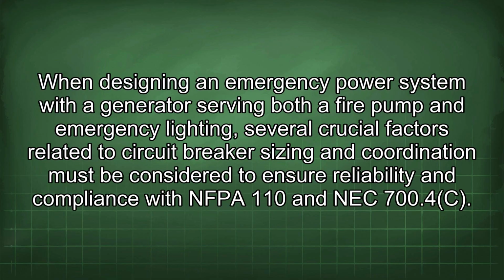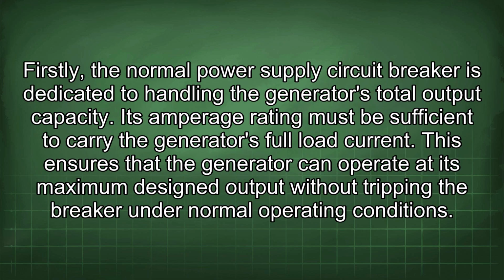When designing an emergency power system with a generator serving both the fire pump and emergency lighting, several crucial factors related to circuit breaker sizing and coordination must be considered to ensure reliability and compliance with NFPA 110 and NEC 700.4c. Firstly, the normal power supply circuit breaker is dedicated to handling the generator's total output capacity. Its amperage rating must be sufficient to carry the generator's full load current. This ensures that the generator can operate at its maximum designed output without tripping the breaker under normal operating conditions.